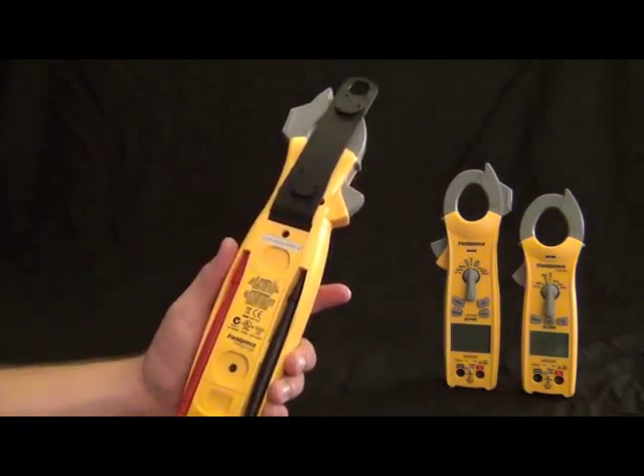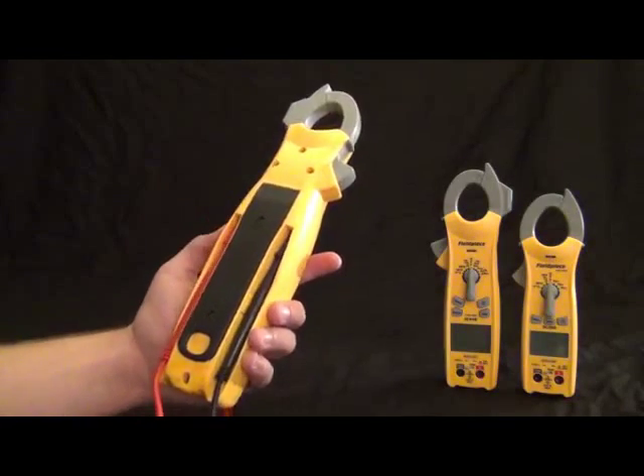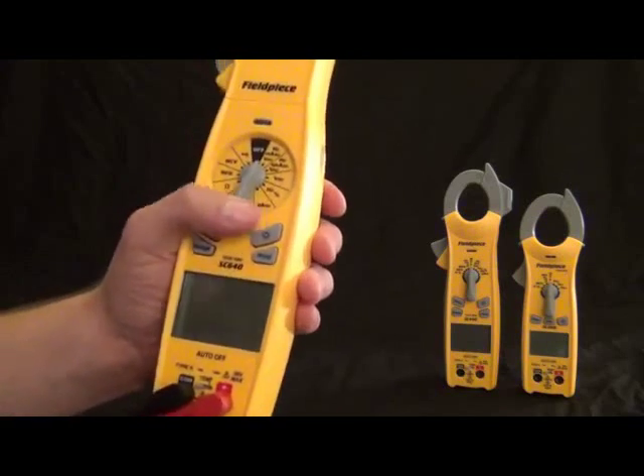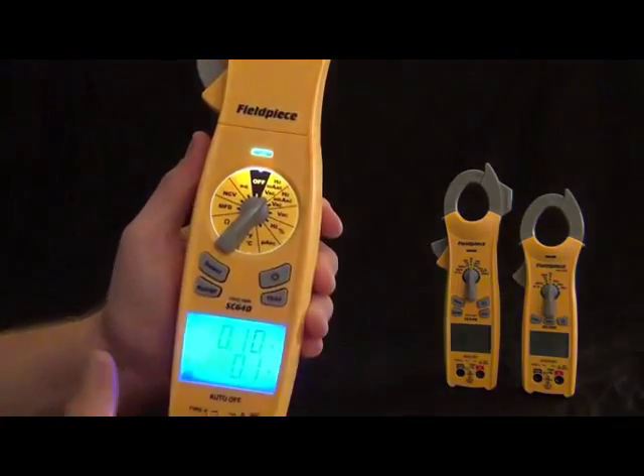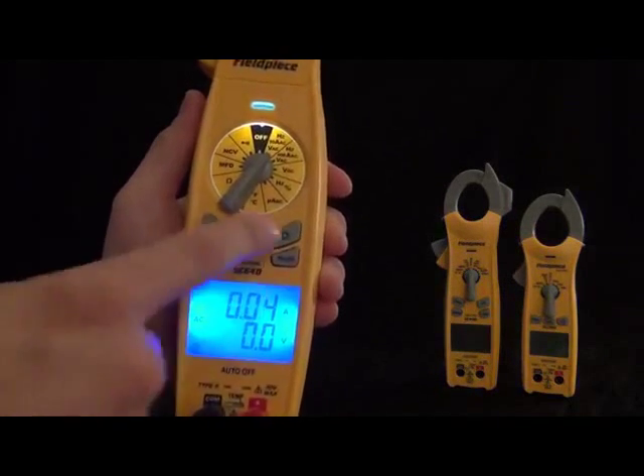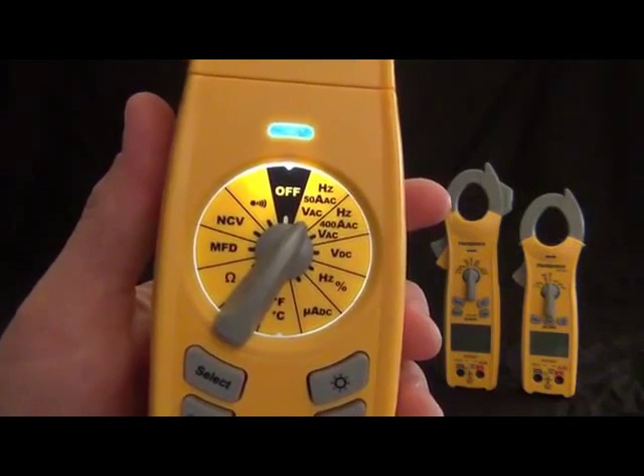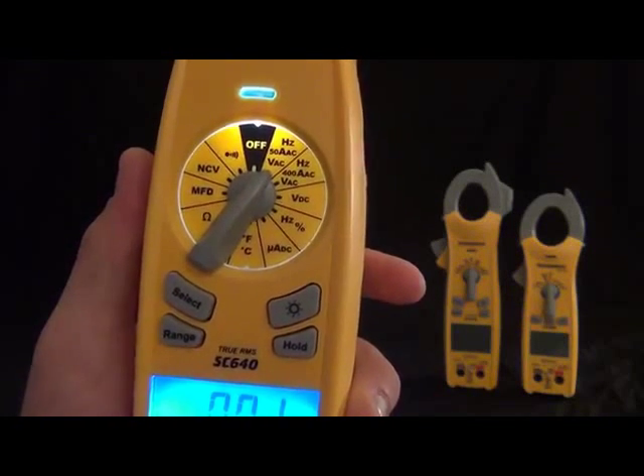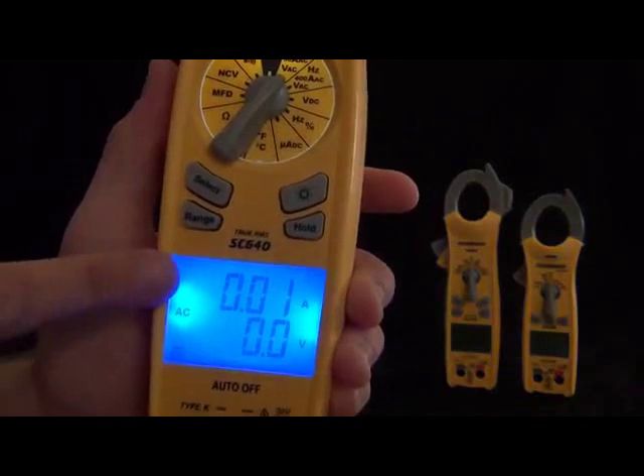Back to the dial. The first thing you'll notice is its backlit display — the dial as well. When you press the backlit button, it also lights up that dial so you can see it in hard-to-reach places. The first switch position is the hertz, amps, and volts AC range. That puts amps in the top display, volts in the bottom display, and also hertz. Hertz and amps are measured with the clamp, and volts with the leads. That's the 50 A AC range and the 400 A AC range.